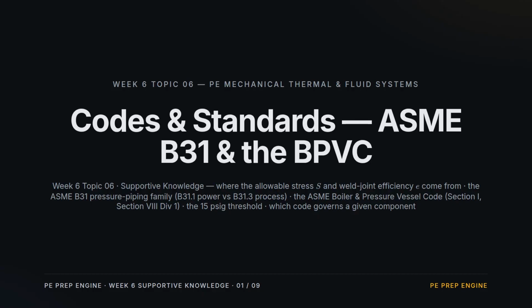Topic 6 of Week 6, Supportive Knowledge, Codes and Standards, the ASME B31 Piping Codes, and the Boiler and Pressure Vessel Code. Last topic, we sized a wall from an allowable stress and a weld joint efficiency, and treated both as given. This lesson opens the documents that set them. No formulas today. The skill is recognizing which code governs a given component and remembering one number, 15 psi gauge.